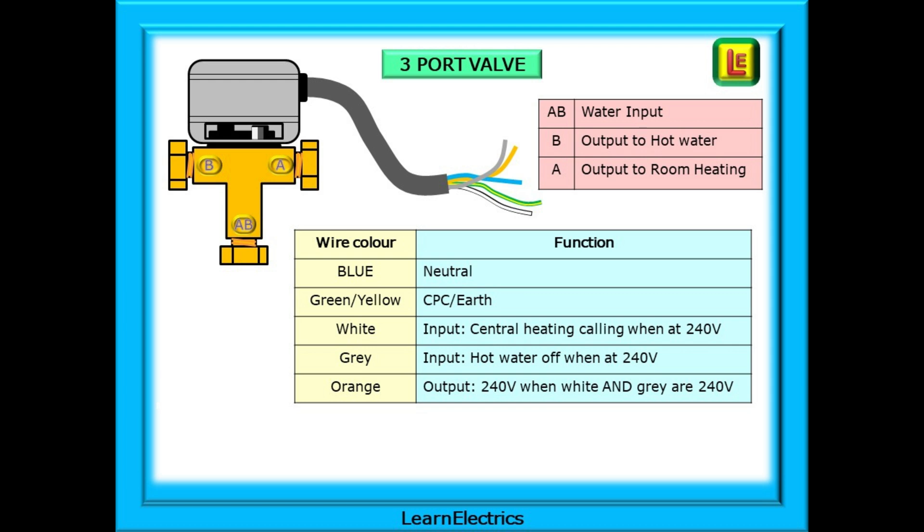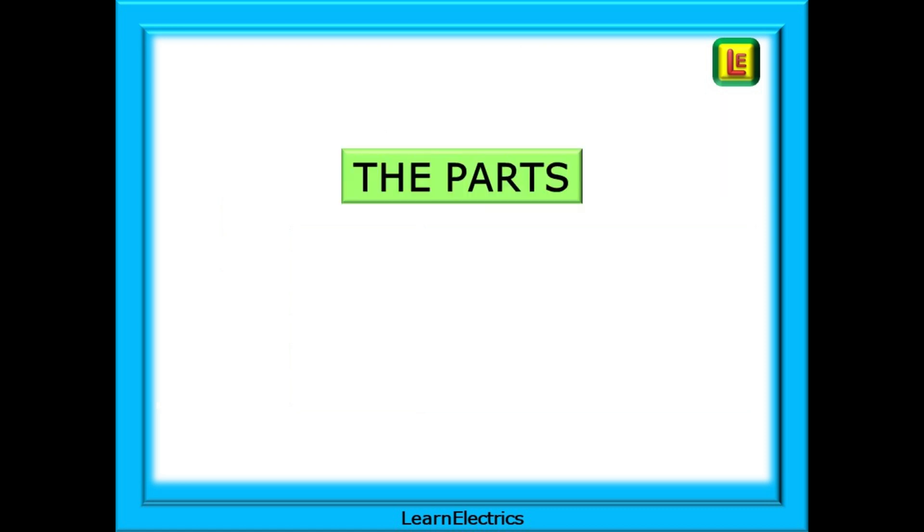The orange wire is an output. If the white wire input and the grey wire input are both at 240 volts at the same time, then the orange wire will output 240 volts. Let's take a simple look at how the various parts function. What do we expect them to do at different times? And we've already looked at the three port valve.